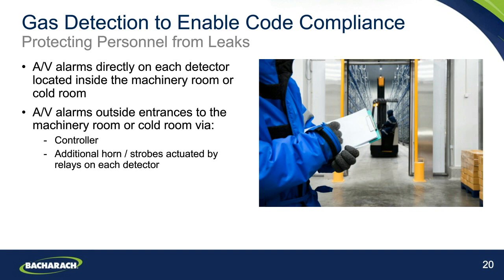Typically, what you'll need to do there is look for a gas detection controller that is working with the devices that can either provide those alarms or drive them. Or you could be looking to use additional horns and strobes, which most typically would be actuated by relays on each gas detector that will trigger in the event of an alarm and provide that additional audio-visual indication outside of the monitored space.